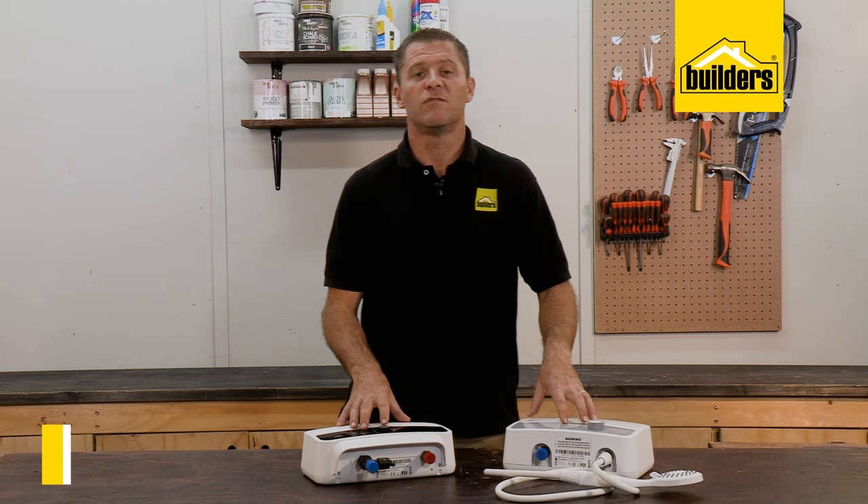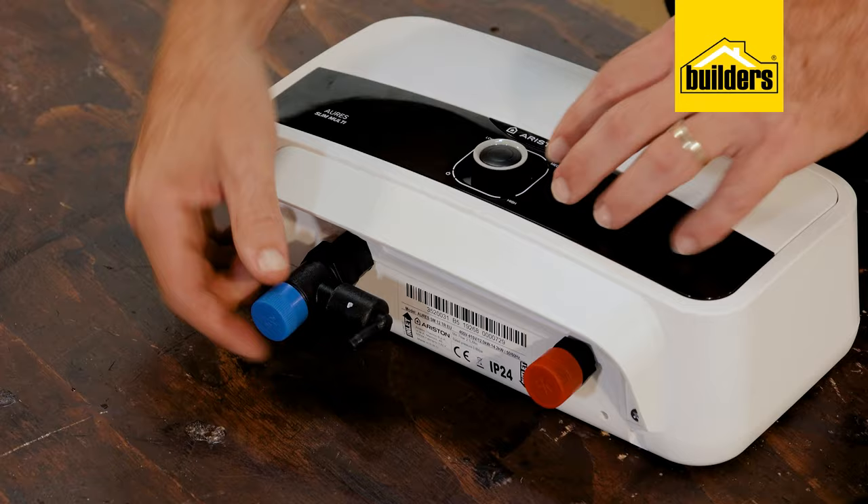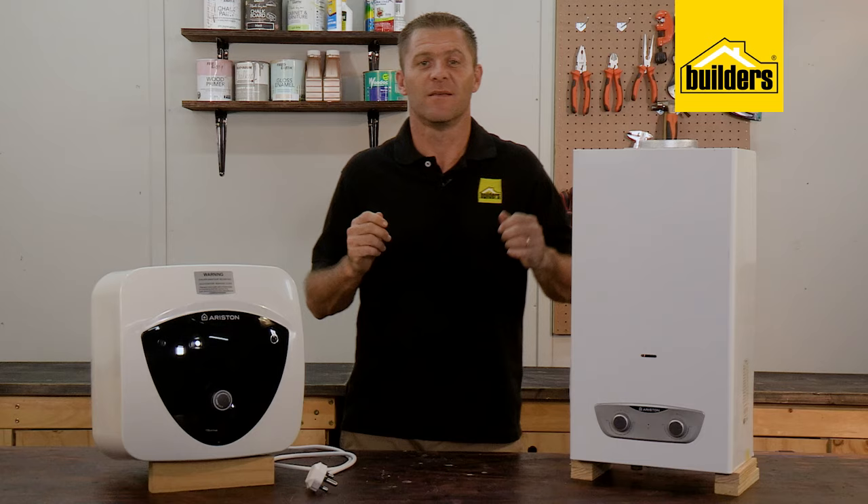The Aures Slim comes with a shower head attachment, but both of these need to be installed by a qualified electrician. They need their own separate circuit with a circuit breaker in the distribution board — these are not plug-and-play systems and certainly not designed to run on an extension lead. The plumbing is fairly simple once the electrician has done their job.